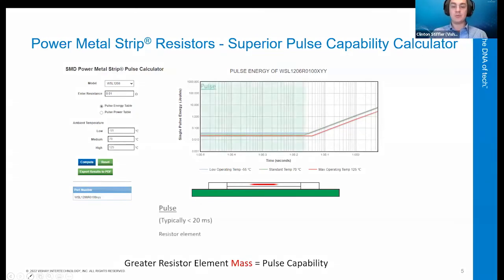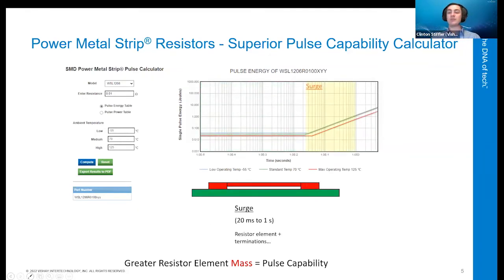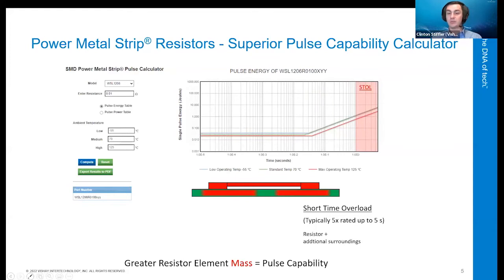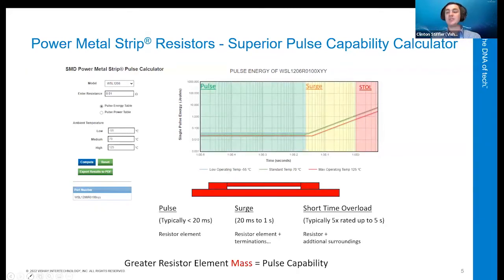The first zone is defined as the pulse, which is generally less than 20 milliseconds. This is a short transient that is caused by a temperature rise in the resistance element. The transient is too fast to dissipate to the surroundings, so the energy is limited to the mass of the resistance element and the thermal limit. As the pulse duration extends into the surge region of time, the energy can transfer to the terminals. This increases the mass available for dissipation, and so the energy capacity increases. And the last zone is known as the short time overload rating, which defines the maximum energy capacity for the part, including the circuit board.